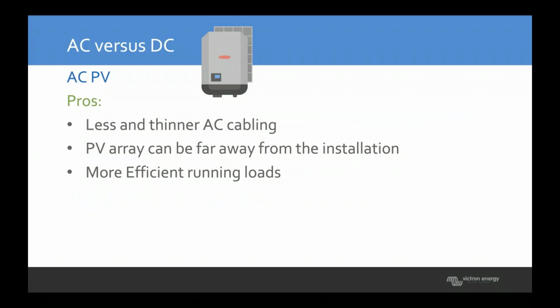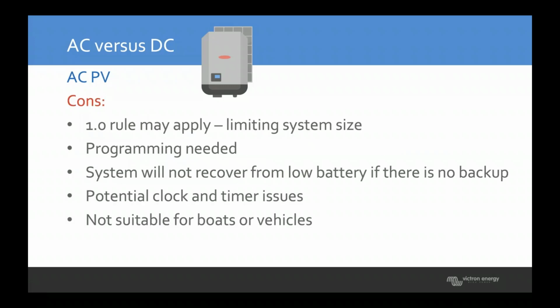Now, one of the other pros of AC PV is less and thinner AC cabling. So you can run solar arrays from further distances away. You don't need as many wires. You can run higher voltage strings. So everything becomes a lot more efficient on the wiring side, including the speed of installation and other things. The cons, though, if in your off-grid situation, or when the AC PV is connected to the output of the multi instead of the input, the one rule may apply. So this limits the system size to the size of the inverter charger. You also need to do extra programming steps.